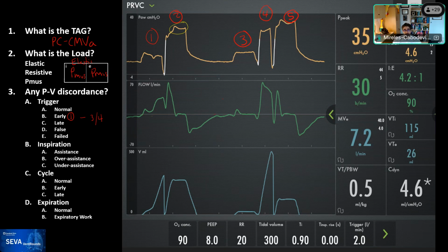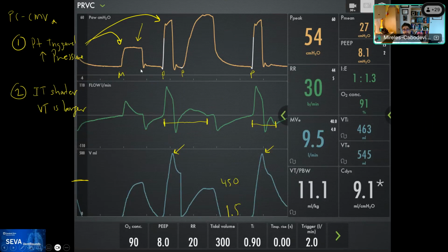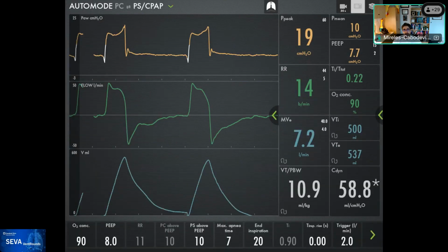We also talked about the different ways that PRVC can be implemented in different ventilators. And this is one that was a surprise for us, and we learned as we took care of patients. It was that the mandatory, machine-triggered, and patient-triggered breaths had different algorithms, and that there's a safety feature that cycles the breath when it delivers 1.5 times the tidal volume that you have set when you're on PRVC or on volume support. And finally, there are different types of auto mode that can help you deal with these interactions, and then you have to make a decision of, well, is this safe target of tidal volume appropriate for this patient or not, and make decisions about how you're going to take care of them.